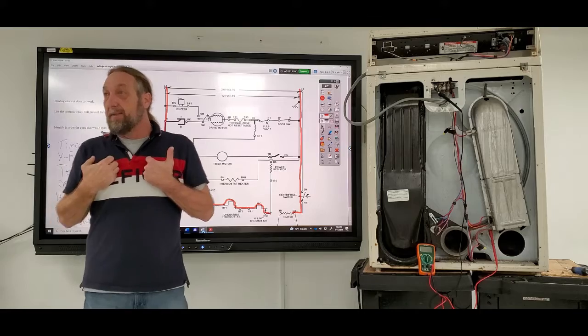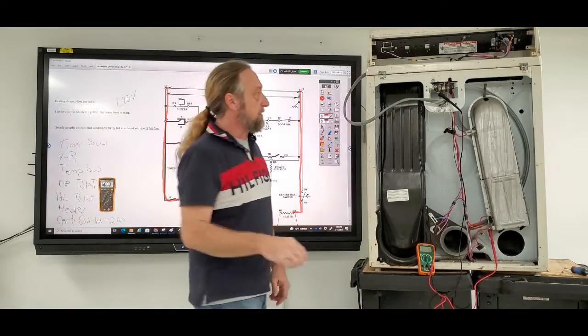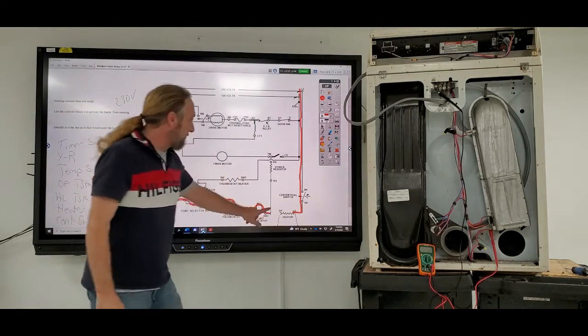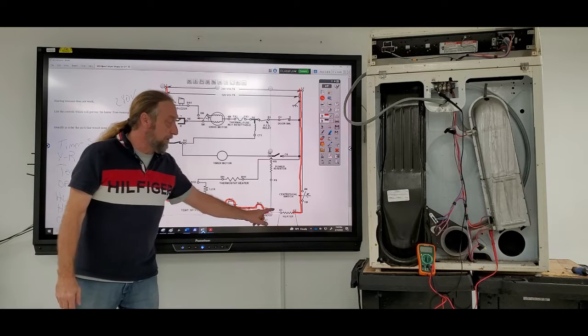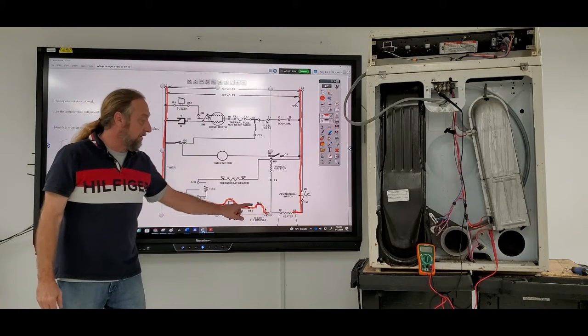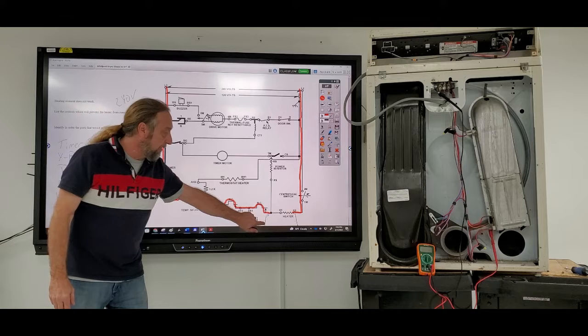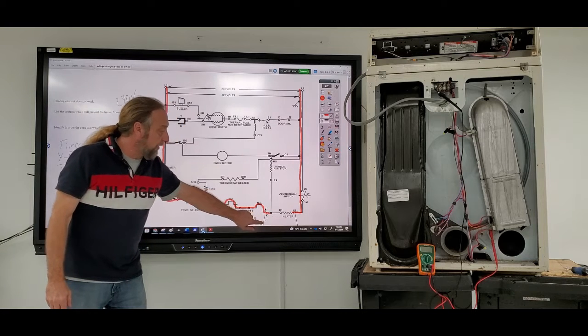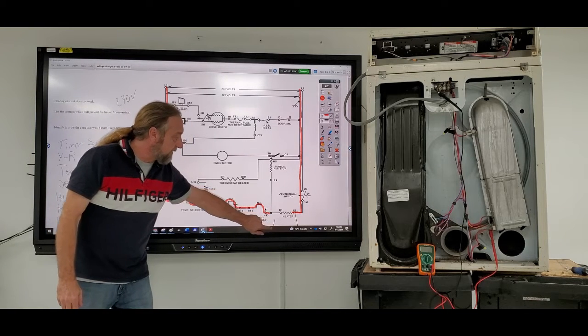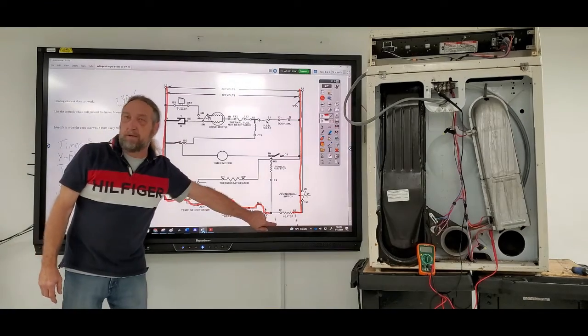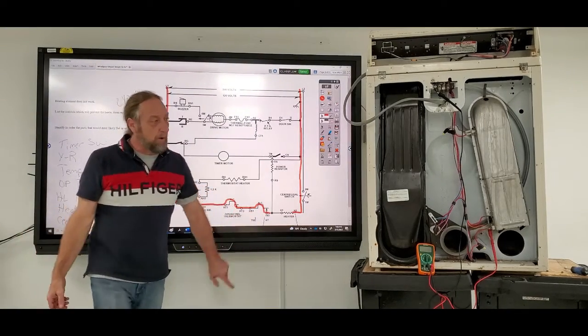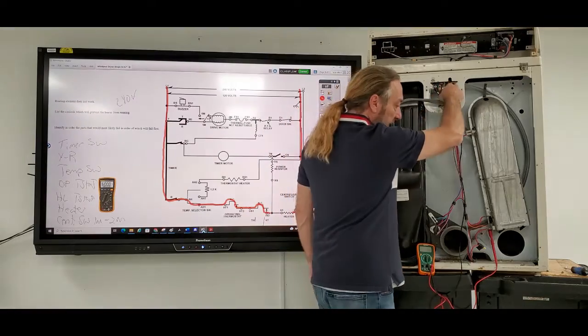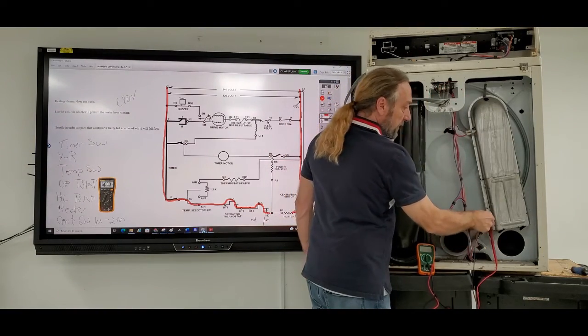But what I would have done then, after that one test, is go back and start backtracking here and here, high limit thermostat, both sides, here and here. So I move it from here to here. What's in between this test and this test? Just a wire. So I'm going to go from this heater here to the high limit thermostat.